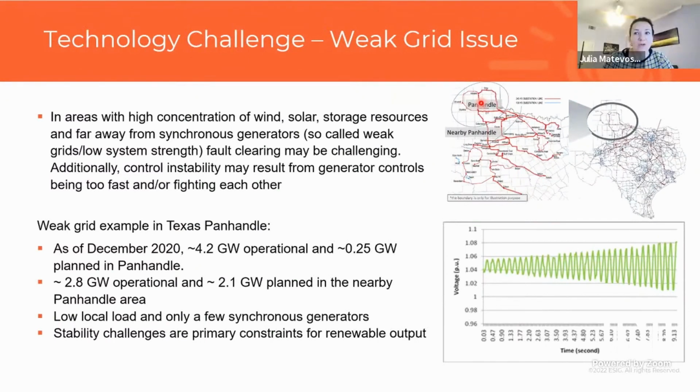So I'm not sure, because say for example in GB, I haven't read the final report from that oscillation event, but last time I heard them talking about it, it was a few months after the event happened. They still couldn't find what the cause was. In ERCOT, from my experience, they had these 3 causes of oscillation, so it's relatively easy. Maybe that's because of how the grid is, that you have these isolated areas with inverter-based resources, nothing else there. So it's more of a clear-cut case.